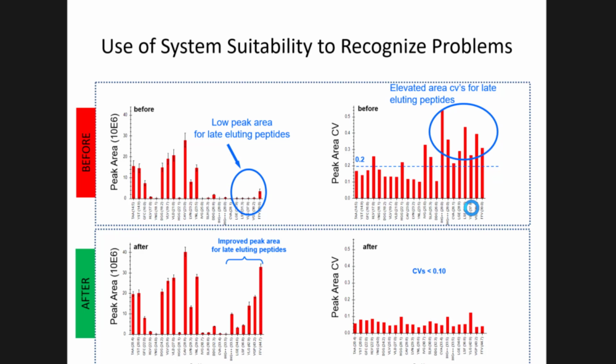So after we pointed this out, they asked, oh, what's going on? They had an Eksigent pump where you calibrate your flow, you measure your flow, and then you can calibrate it by inputting, I forget, a period of time that you're going to calibrate it over or something, and whoever did it put the wrong value by half for pump B. And so the acetonitrile that was being delivered over the gradient is low at the beginning, and pump B is working harder at the end.